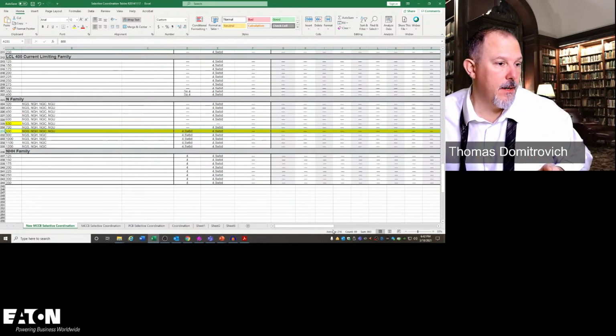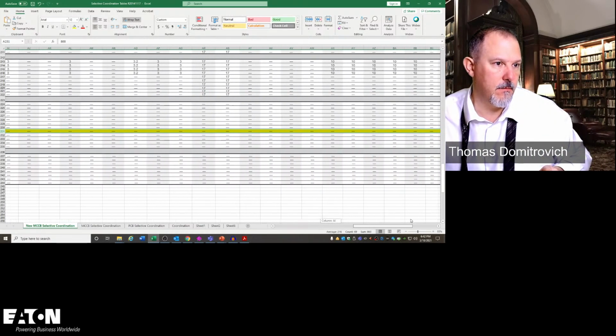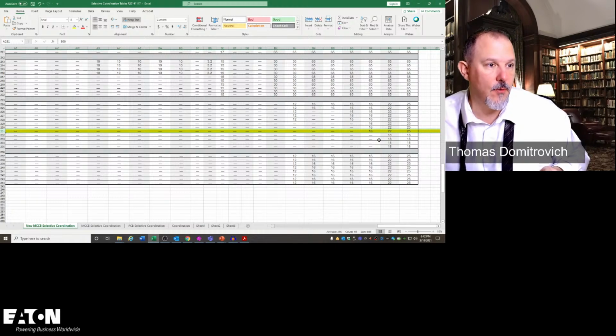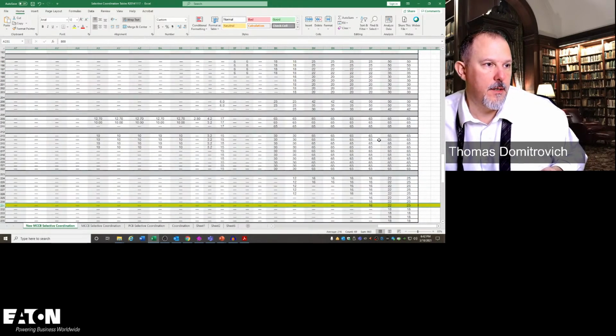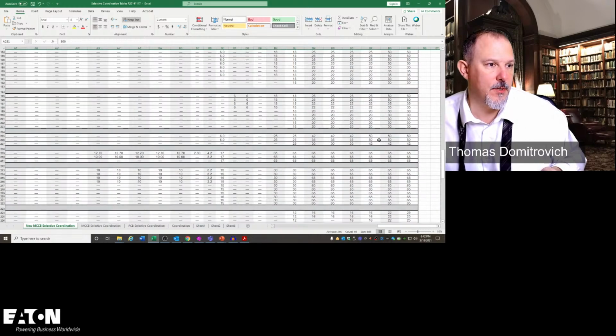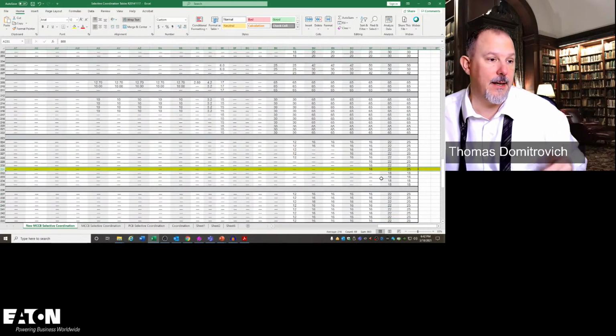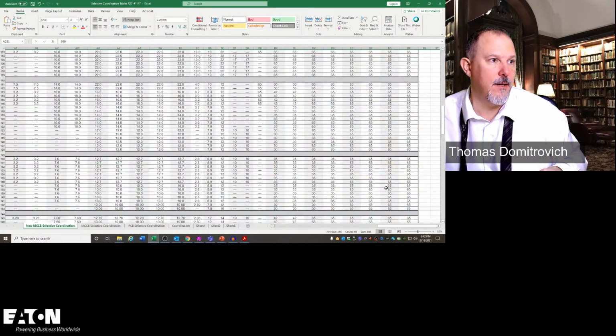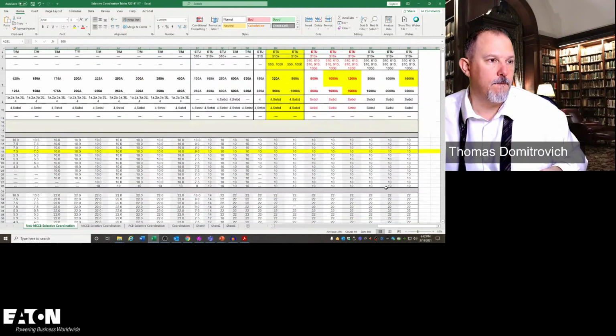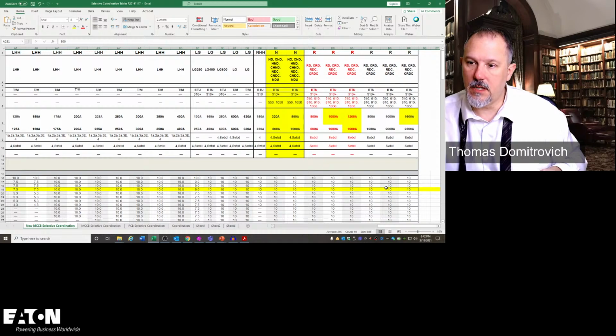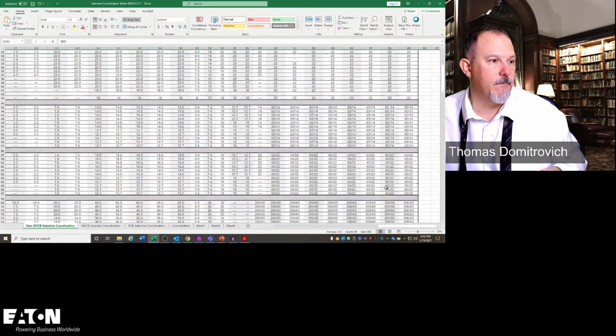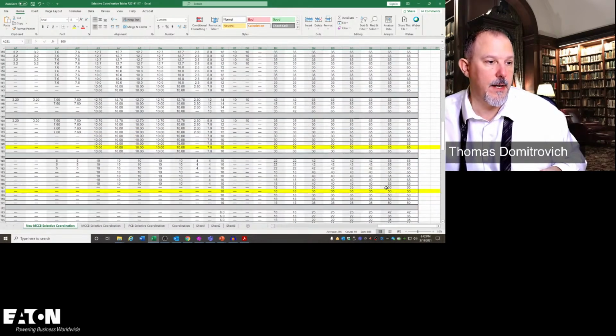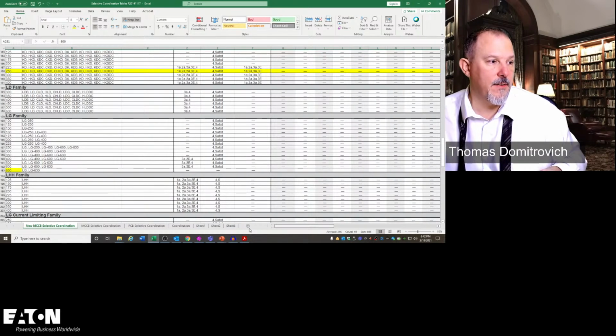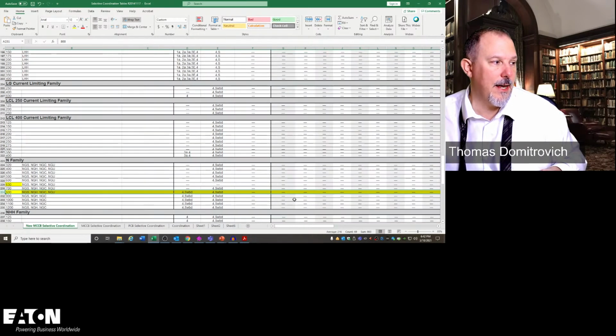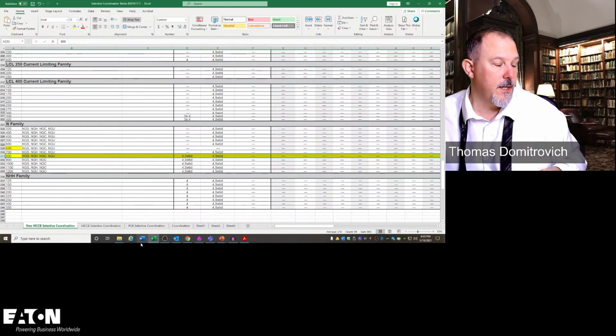So my N frame breaker, I don't have the tables. I can't leverage my tables in this regard because I don't have a tested pair that's downstream. Look at the table values and then multiply by K. Yeah, you could do that. You could do that. So I've got 5,000 amps, and now here's the other thing I could do.